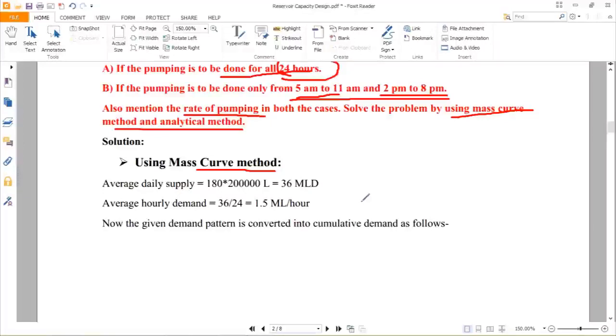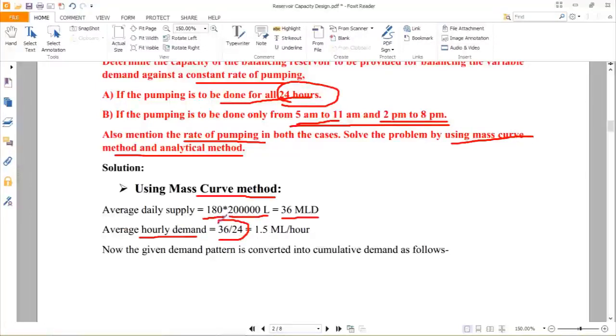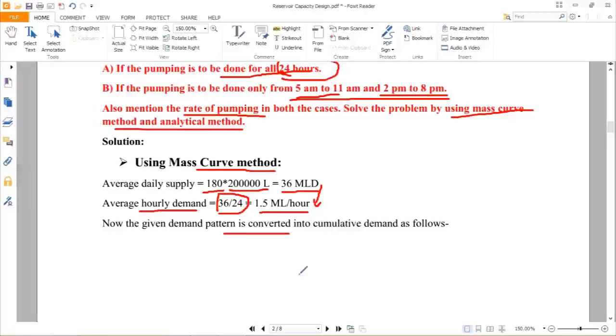Solving using the mass curve method, first for 24-hour pumping: the population is 2 lakhs and demand is 180 lpcd. Average daily supply equals 180 multiplied by 2 lakh = 36 million liters per day. The average hourly demand is 36 divided by 24 = 1.5 million liters per hour. Therefore the average hourly supply rate to be maintained is 1.5 million liters per hour.